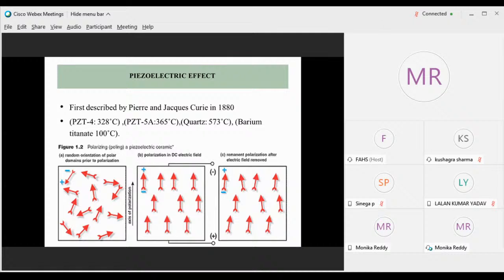But it will depolarize when it exceeds the Curie temperature. So what is Curie temperature? The temperature at which the crystal loses its polarization is known as the Curie temperature. Each crystal has a different Curie temperature. Here we have mentioned that PZT-4 has 328 degrees Celsius, whereas PZT-5A can tolerate up to 365 degrees Celsius. Quartz, a natural piezoelectric crystal, can tolerate 573 degrees Celsius, and barium titanate can tolerate only 100 degrees Celsius. If they exceed these Curie temperatures, they will depolarize and won't be a medical transducer anymore.